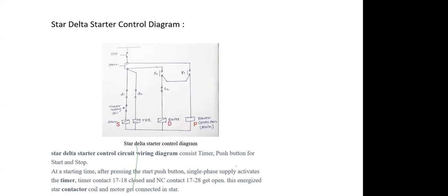The reason is, if the motor has not reached synchronous speed at the transition, the current is still going high. Now if the connection suddenly changes, there is a momentary gap between star getting deactivated and delta getting connected. You will not feel it, but there is a gap. So there is a sudden jerk in the entire electrical system.